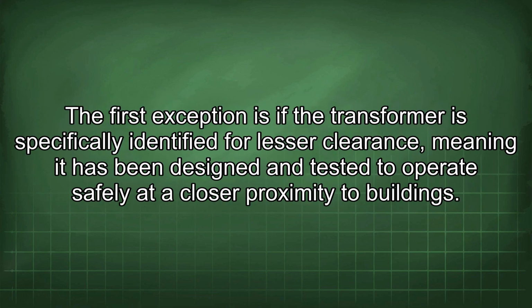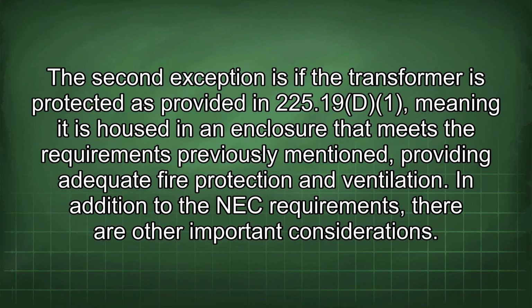The first exception is if the transformer is specifically identified for lesser clearance, meaning it has been designed and tested to operate safely in closer proximity to buildings. The second exception is if the transformer is protected as provided in 225.19d, meaning it is housed in an enclosure that meets the requirements previously mentioned, providing adequate fire protection and ventilation.